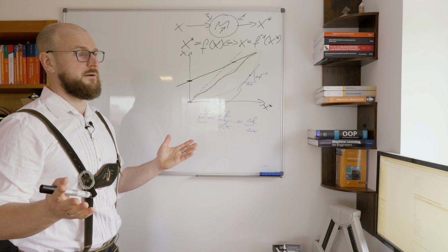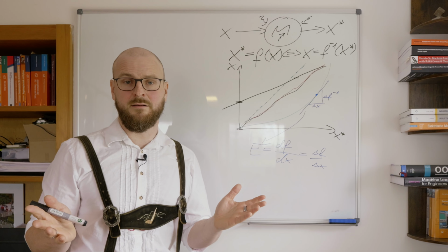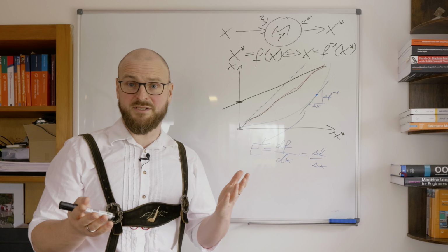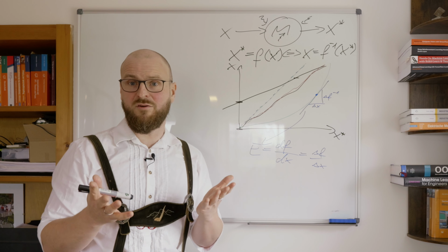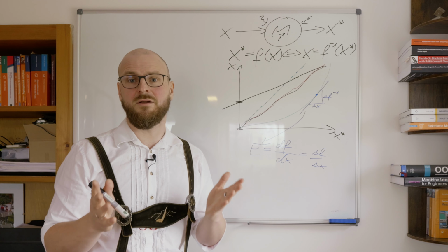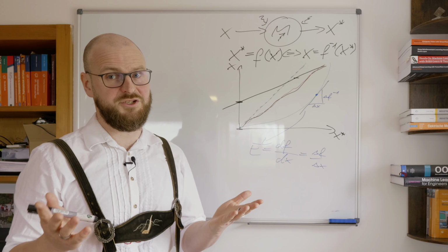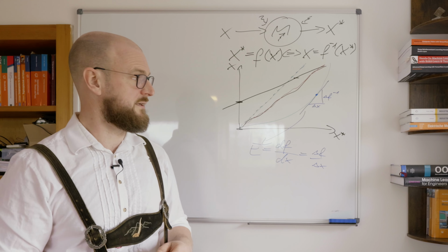It's the normal way you would define a sensor signal. Sensor signals should be above 0. When a 0 signal gives you important information about your measurement, that's not good, because when the sensor is defective, it would give you some information which actually has to be wrong, because the sensor is defective.